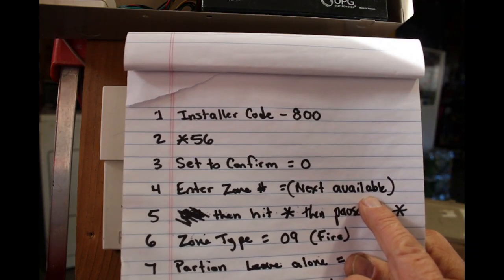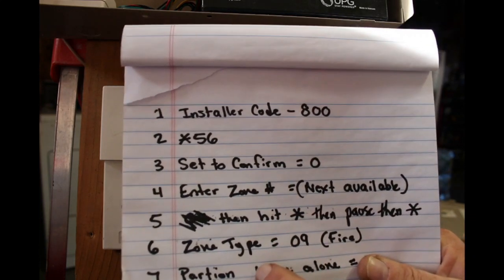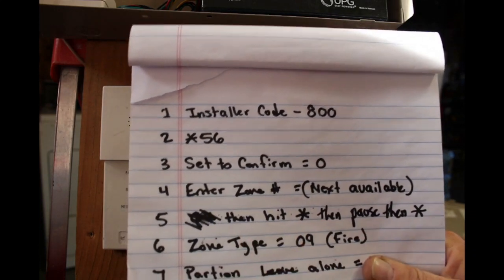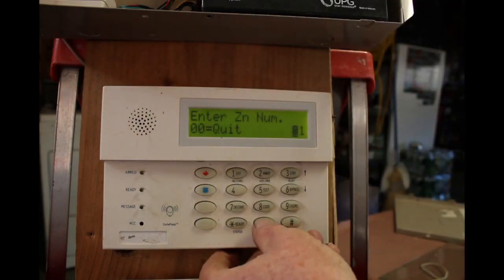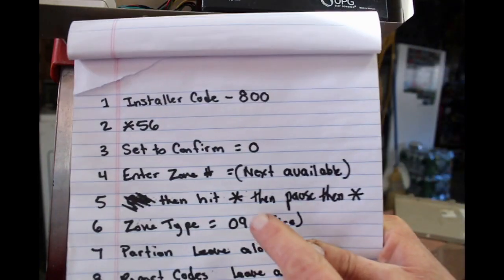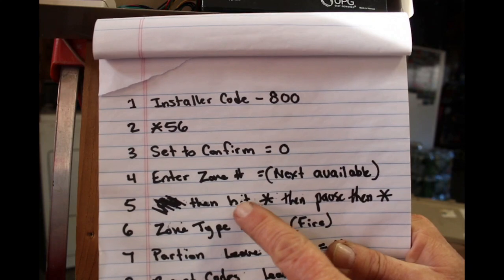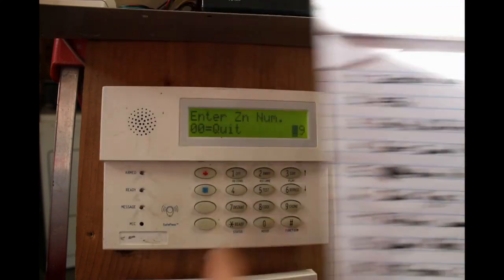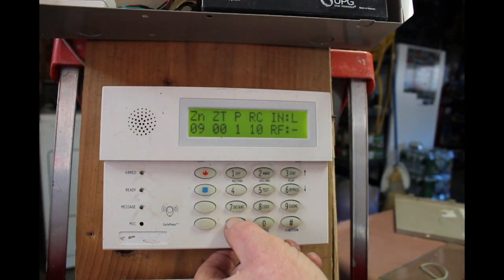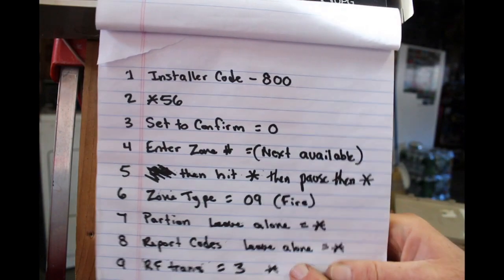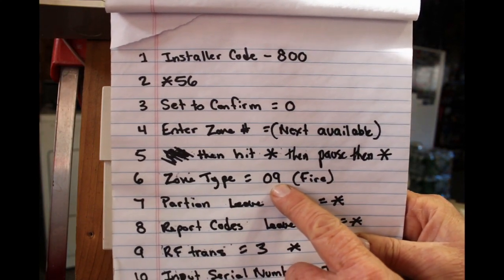Enter zone number, that's the next available that you have. If you don't know what yours is, go up to like 16 and most likely that's going to be available for you. My next zone number that's available is 09, so I'm going to hit 09. All right, so I hit the next available zone, and then it says hit star, then pause, and then hit star. So hit star, you pause a second, then you hit star. Zone type: you're going to be doing a fire alarm, so you put in 09.